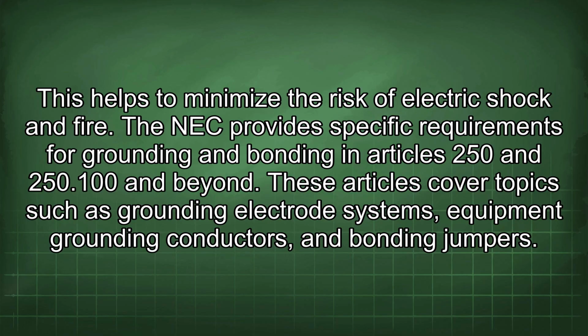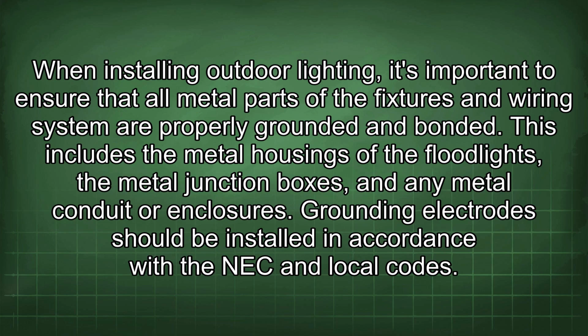The NEC provides specific requirements for grounding and bonding in Article 250, including 250.100 and beyond. These articles cover topics such as grounding electrode systems, equipment grounding conductors, and bonding jumpers. When installing outdoor lighting, it's important to ensure that all metal parts of the fixtures and wiring system are properly grounded and bonded. This includes the metal housings of the floodlights, the metal junction boxes, and any metal conduit or enclosures. Grounding electrodes should be installed in accordance with the NEC and local codes.